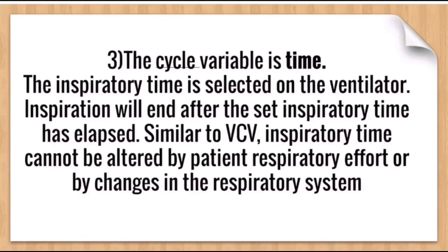Similar to volume control ventilation, inspiratory time cannot be altered by patient's respiratory efforts or change in the respiratory system. Here we have directly set the inspiratory time, while in case of volume control ventilation, we have indirectly set the inspiratory time by setting the flow and by setting the tidal volume.